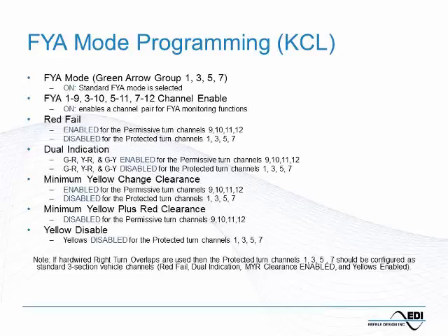The difference being that the ECL models, whether it's 2010 ECL or 2018 ECL, one is a 16, one is an 18 channel monitor. For the 2018 KCl, all of the programming is done with a data key. So there are no dip switches, there are no diodes to cut. We program in the data key, actual configuration data, and away we go.